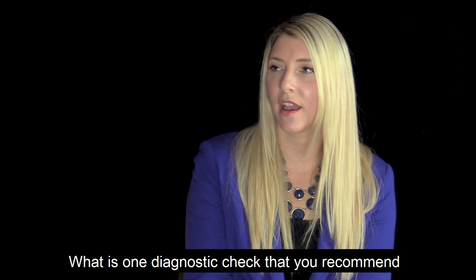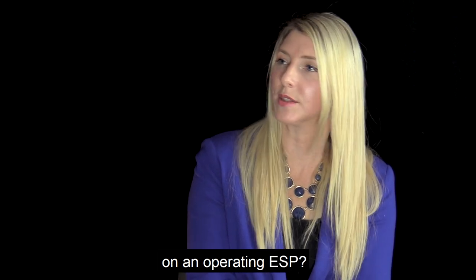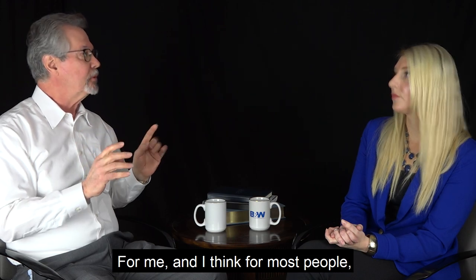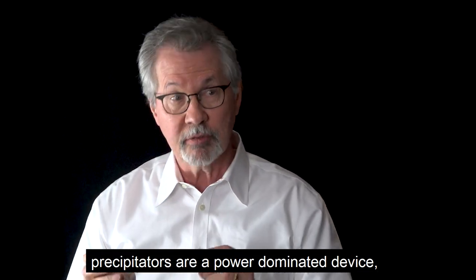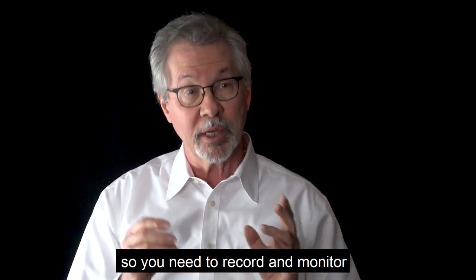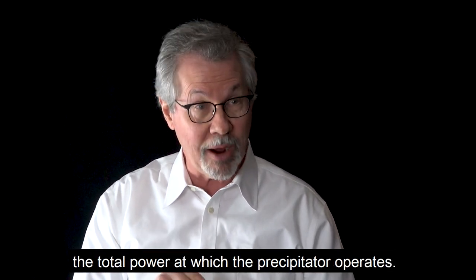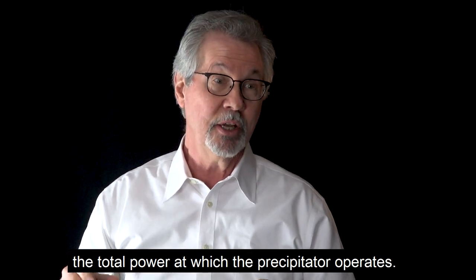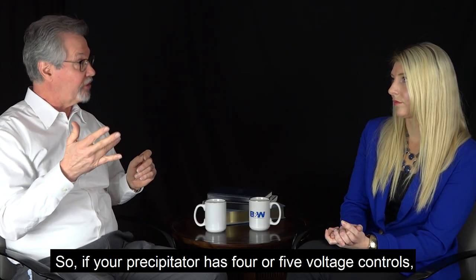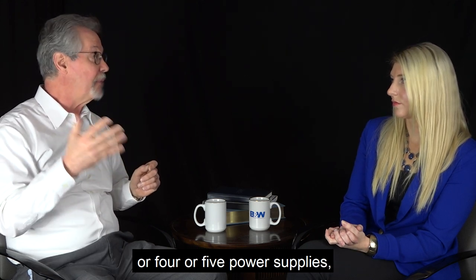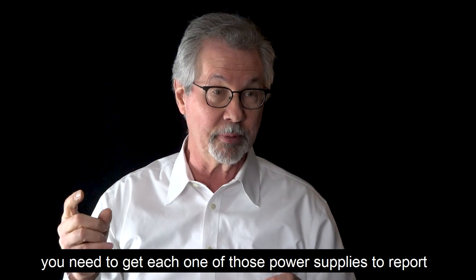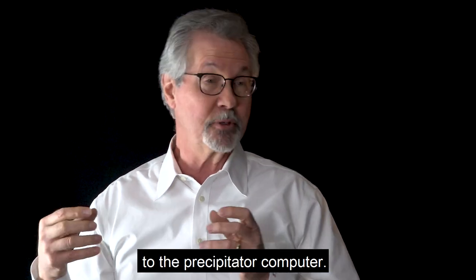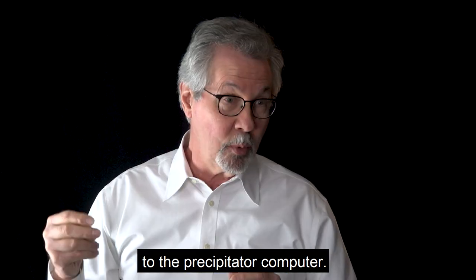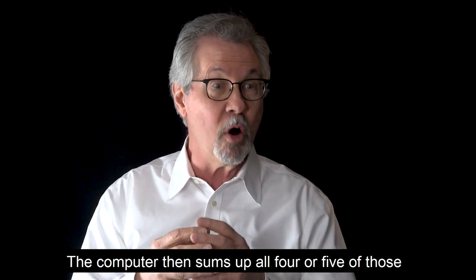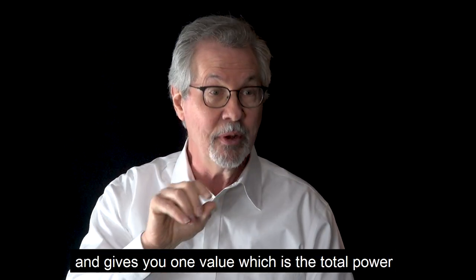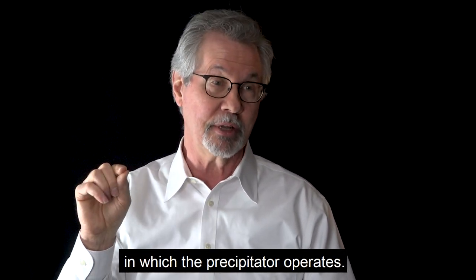Great. What is one diagnostic check that you recommend on an operating ESP? For me, and I think for most people, since a precipitator is a power-dominated device, you need to record and monitor the total power at which it operates. So if your precipitator has four or five voltage controls or power supplies, each one reports its power to the precipitator computer. The computer then sums up all four or five values and gives you one total power reading for the precipitator.